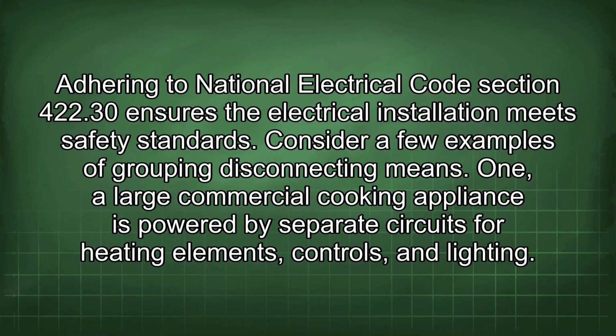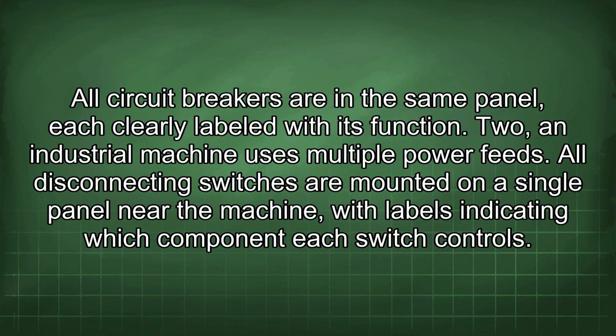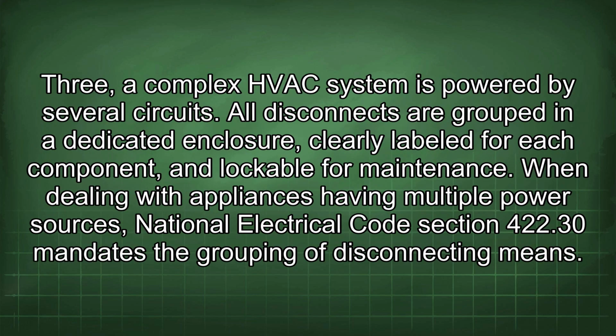Consider a few examples of grouping disconnecting means. 1. A large commercial cooking appliance is powered by separate circuits for heating elements, controls, and lighting. All circuit breakers are in the same panel, each clearly labeled with its function. 2. An industrial machine uses multiple power feeds. All disconnecting switches are mounted on a single panel near the machine, with labels indicating which component each switch controls. 3. A complex HVAC system is powered by several circuits. All disconnects are grouped in a dedicated enclosure, clearly labeled for each component, and lockable for maintenance.